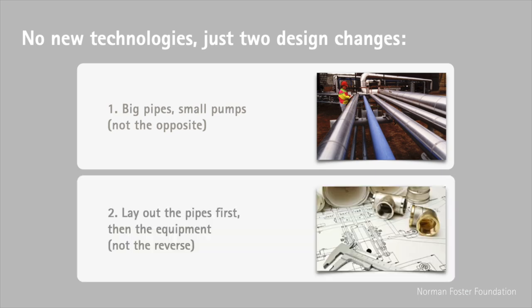Now, the second shift in design is even simpler, therefore harder, and that's to lay out the pipes first, then the equipment. Traditionally, we put the tanks, boilers, whatever, in convenient, arbitrary, traditional places, and then we call in the pipe fitter to please come connect point A to point B. But by then, they'd be a pretty far apart.